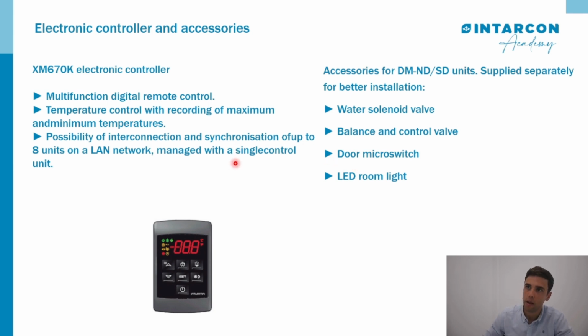Electronic control: we are going to work with the XM670K electronic control. That is a parametric control that uses a multifunction digital remote control, temperature control with recording of the maximum and minimum temperature, and the possibility of interconnection and synchronization of up to 8 units on a LAN network.